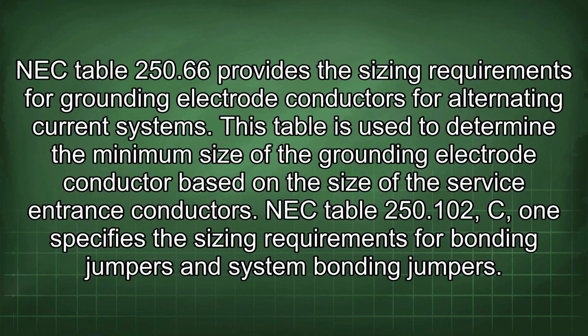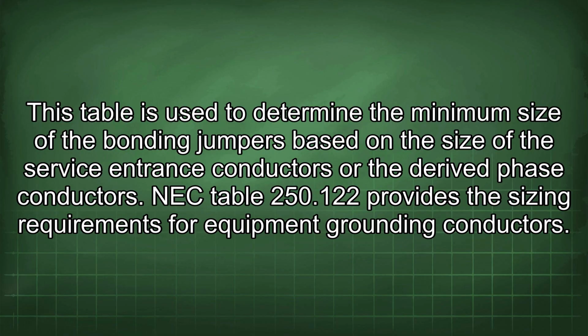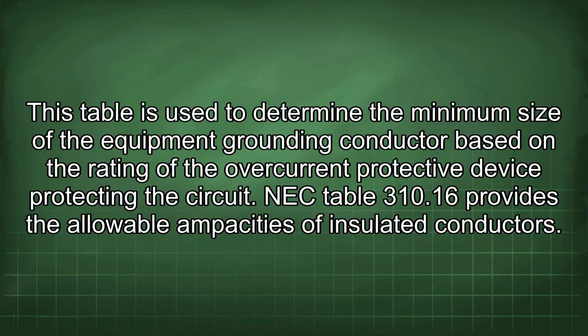250.102(C)(1) specifies the sizing requirements for bonding jumpers and system bonding jumpers. This table is used to determine the minimum size of the bonding jumpers based on the size of the service entrance conductors or the derived phase conductors. NEC Table 250.122 provides the sizing requirements for equipment grounding conductors. This table is used to determine the minimum size of the equipment grounding conductor based on the rating of the overcurrent protective device protecting the circuit.